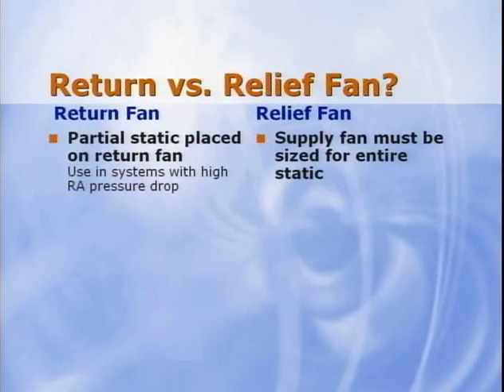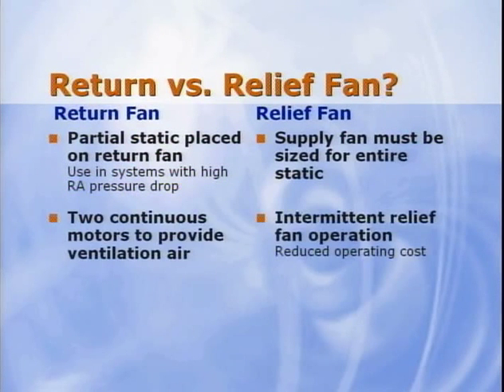So, which is preferred? Both fan systems should be evaluated. But, generally, if the supply fan is capable of handling the pressure drop of both the supply and return air paths, then the relief fan configuration is preferred. As an example, the relief fan configuration works best in VAV systems that use an open ceiling plenum for part of the return air path. When the pressure drop through the return air path is very high, as in some hospitals, again, evaluate both configurations. Use a return fan if the return air path adds more pressure drop than the supply fan can handle. The relief fan can often be turned off during non-economizer hours, while a return fan must run whenever the supply fan is on. Fewer hours of operation usually result in lower operating cost.